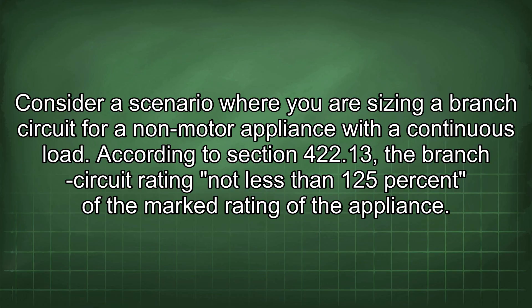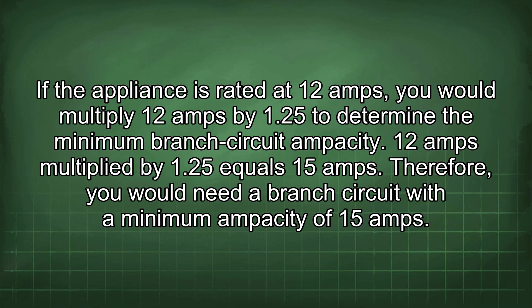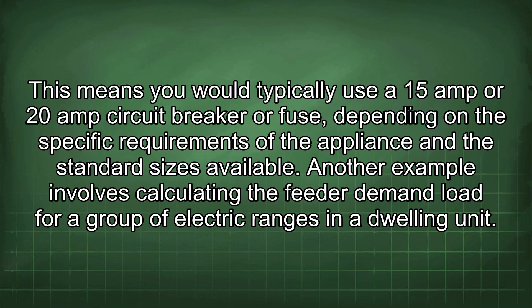Consider a scenario where you are sizing a branch circuit for a non-motor appliance with a continuous load. According to section 422.13, the branch circuit rating must be not less than 125% of the marked rating of the appliance. If the appliance is rated at 12 amps, multiply 12 amps by 1.25: 12 × 1.25 = 15 amps. Therefore, you would need a branch circuit with a minimum ampacity of 15 amps.